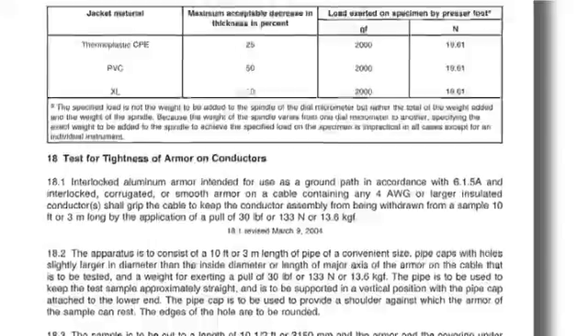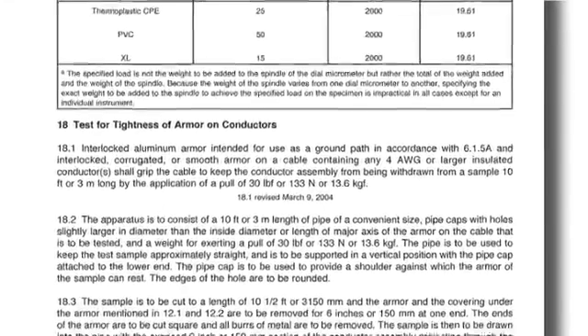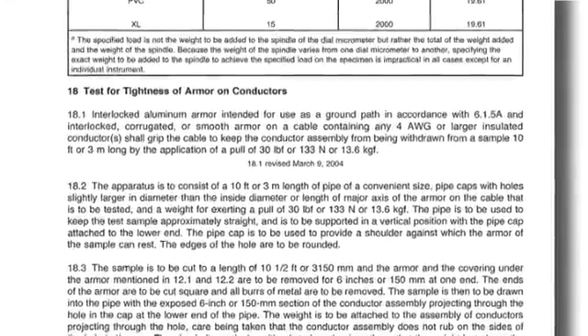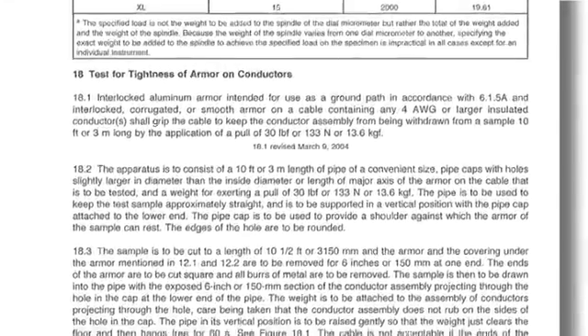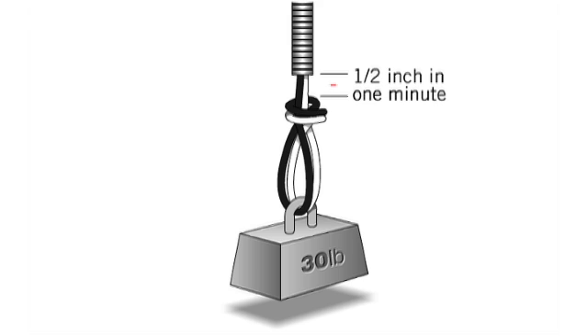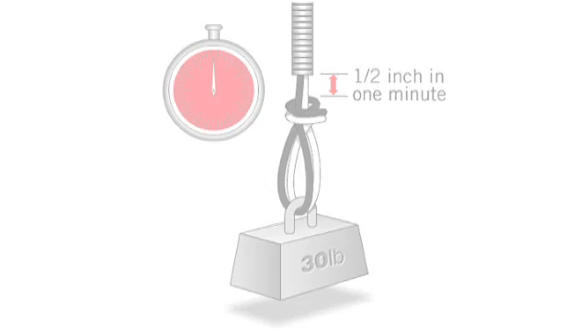The following is a description of the armor tightness test. All assemblies must meet this requirement whether using copper or aluminum alloy conductors containing four gauge or larger conductors. The armor tightness test in UL1569 requires that the conductors in a ten-foot sample of MC cable support a thirty-pound weight. To pass this test, the conductors cannot slip more than one-half inch for the first minute. The conductors can continue to move after the one-minute timeframe has elapsed.